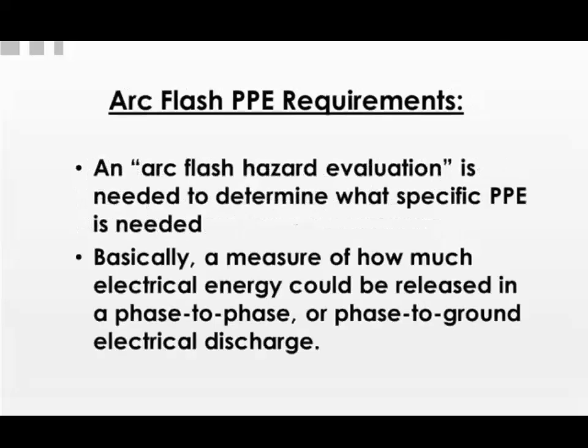Now, we've talked about an arc flash hazard evaluation. An arc flash hazard evaluation is needed to determine what specific personal protective equipment is needed. If your plant hasn't done one, I highly recommend getting it done as soon as possible. Now, I'll warn you, it is not cheap to do. This can run into the thousands or tens of thousands of dollars if you don't have the resources internally to do it. But in my strong opinion, it is money well spent. Basically, it's a measure of how much electrical energy could be released in a phase-to-phase or phase-to-ground electrical discharge, done by a trained, competent electrical engineer.